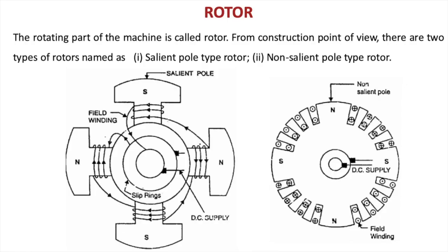Next comes the rotor. The rotating part of the machine is called the rotor. From a construction point of view, there are two types of rotors named salient pole rotor and non-salient pole type of rotor. The salient pole means there will be projected poles, and just by the naked eye you can know the number of poles on the salient pole type of rotor. For the non-salient type of rotor you will have a complete circular circumference, and the conductors will be embedded inside it. So that is the non-salient pole type of structure.